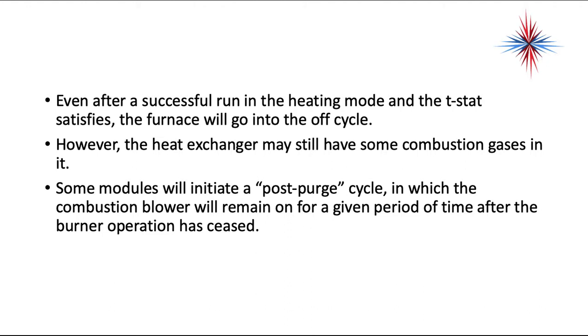Even after a successful run in the heating mode, the thermostat is satisfied and the furnace will go into an off cycle. However, the heat exchanger may still have some combustion gases in it. Some modules will initiate a post-purge cycle in which the combustion blower will remain on for a given time period after the burner operation has ceased.